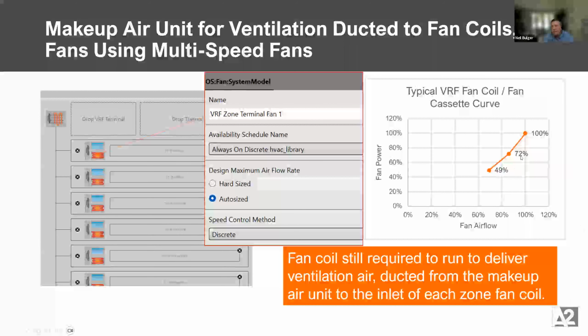So we could say how low is low. Manufacturers will publish the airflow of their lowest speed. It's very hard to find the power rating because it's very directly linked to a design. This was the curve we made after looking at several sites and several fan coils. Most fan coils will not turn down below 70% speed, was the lowest we found in lots of them, and at about 50% power. It's not as much turn down as you might get in other variable capacity fans, but it's definitely something. It's half the power of full flow, and you'll see that in the energy.